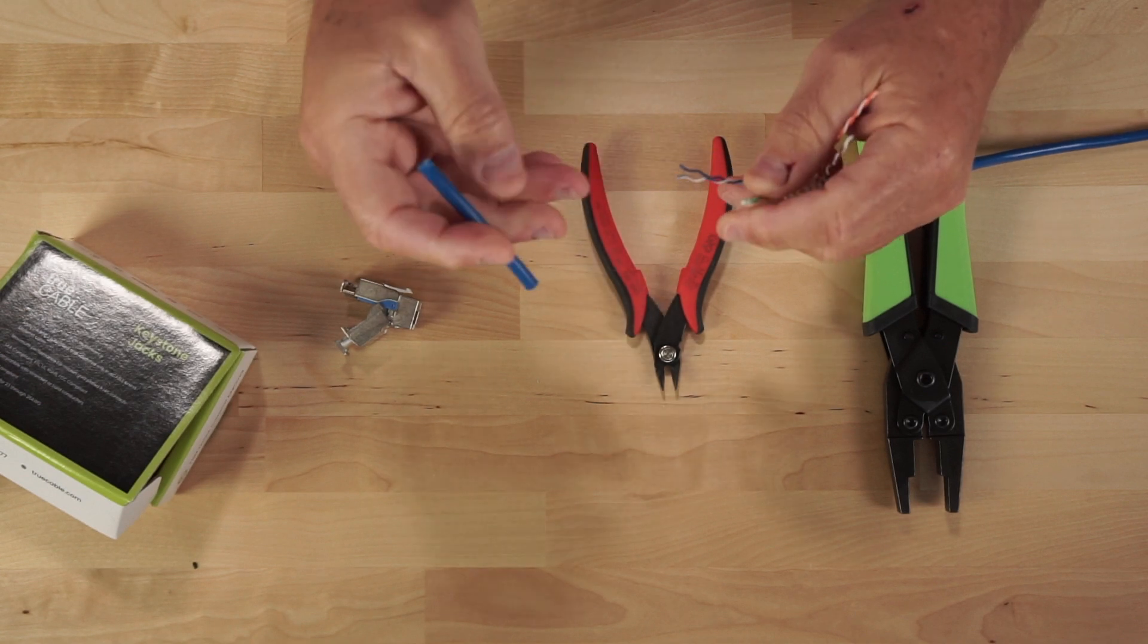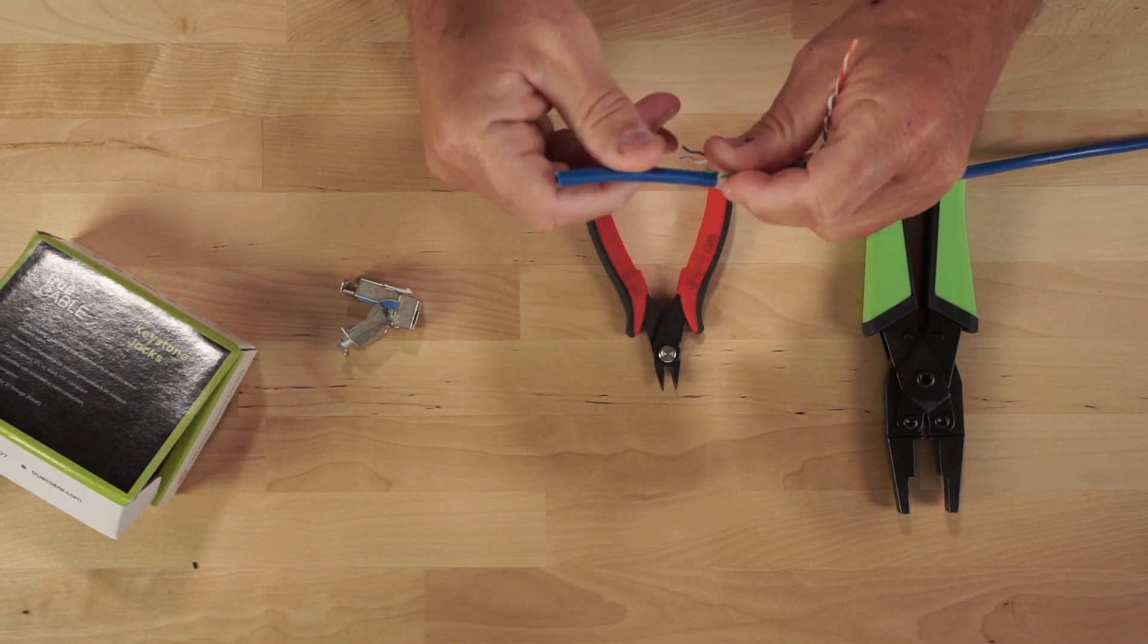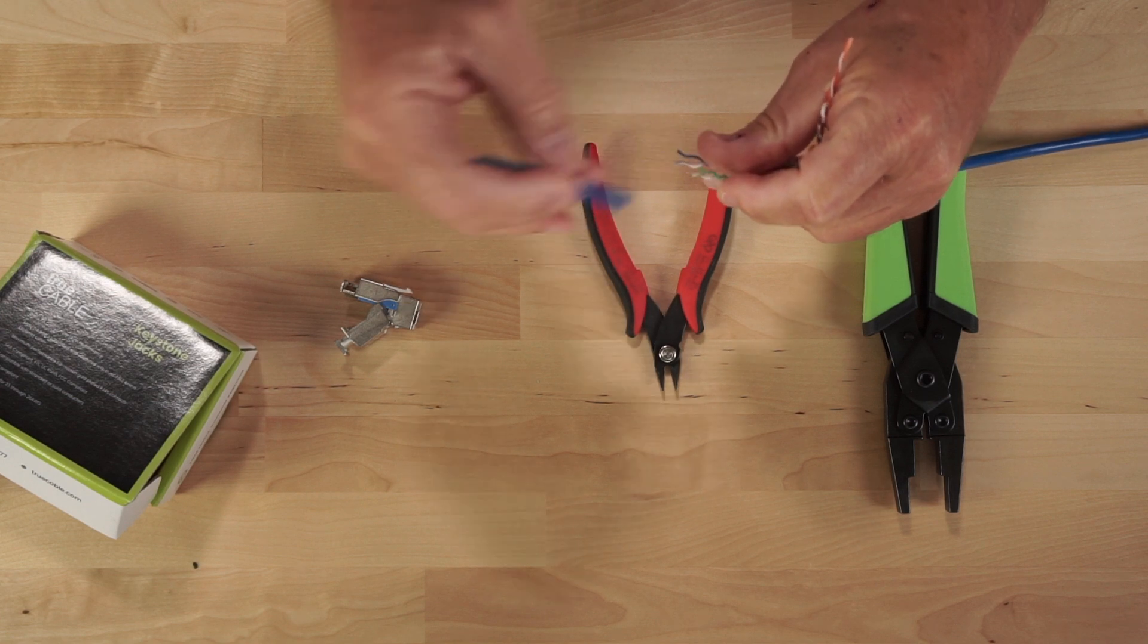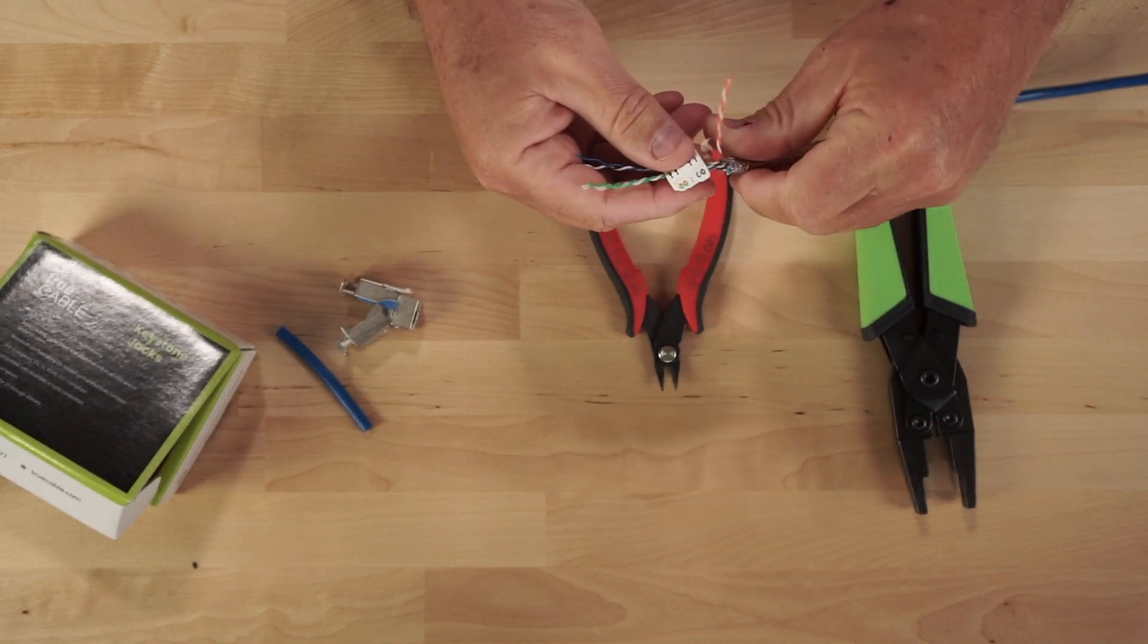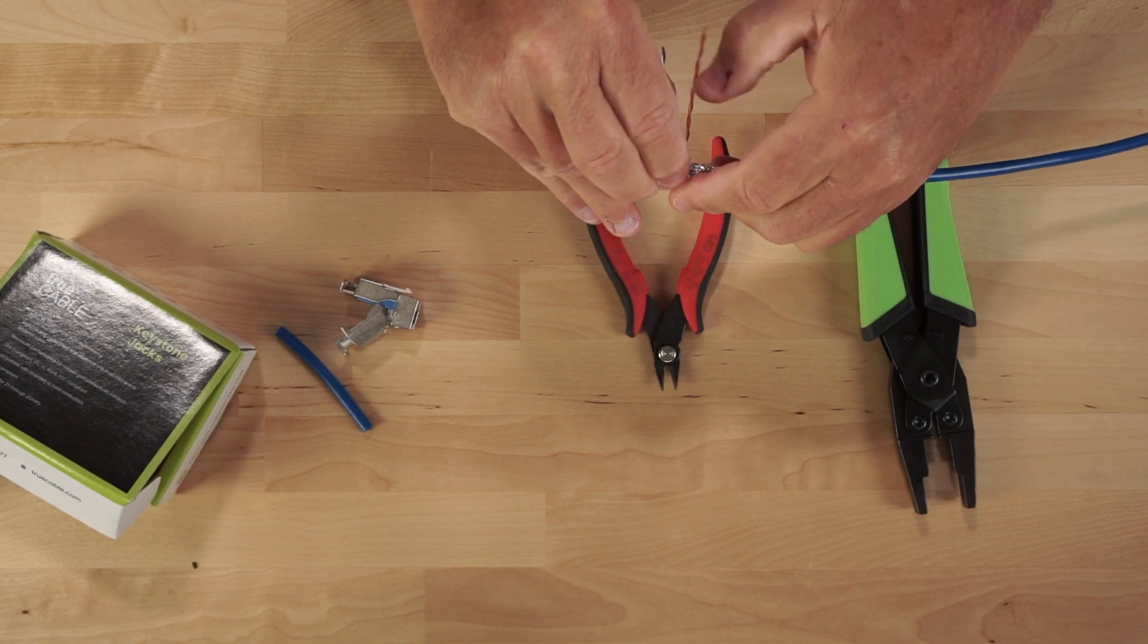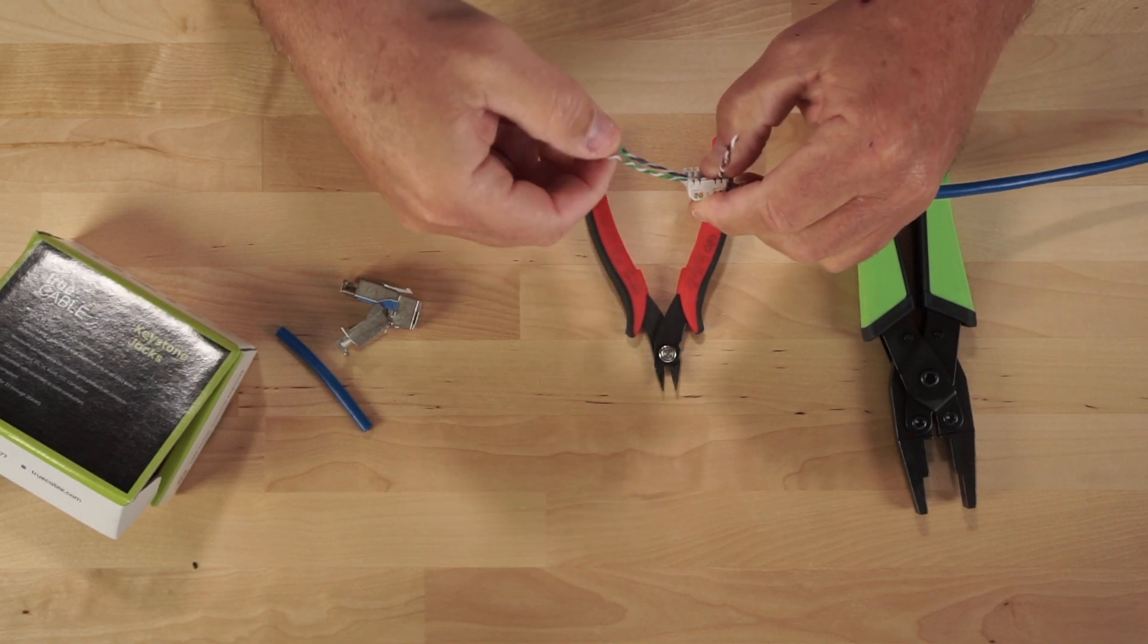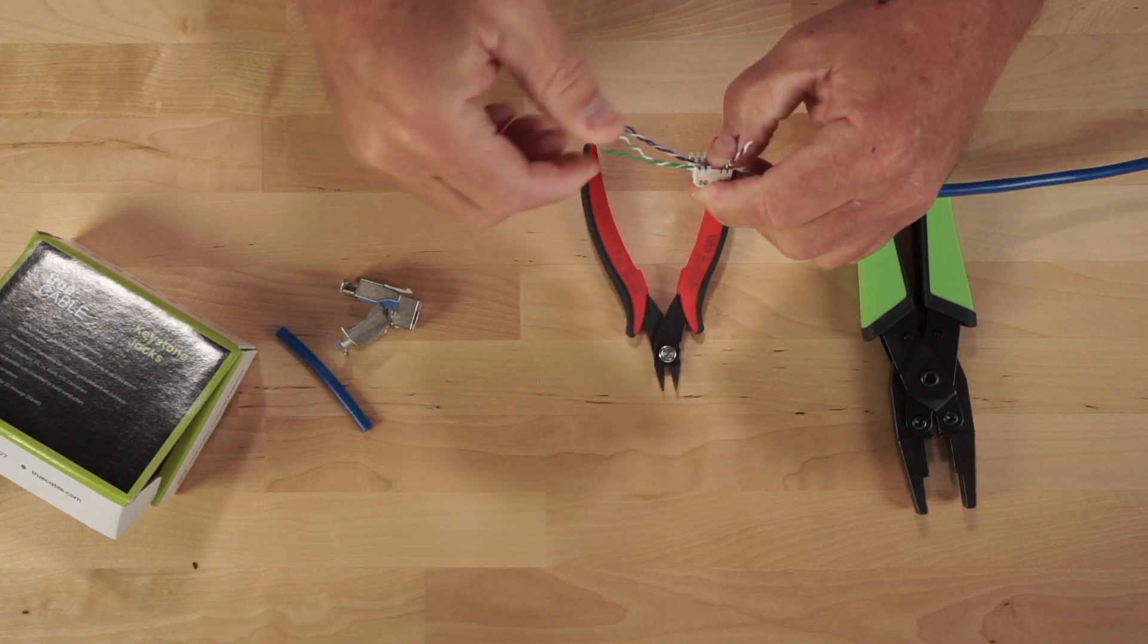I'm not going to open them up all the way because we want to leave them twisted at least a half inch to the punch down point. So we'll get the green pair untwisted to a point where we still have a good enough twist.